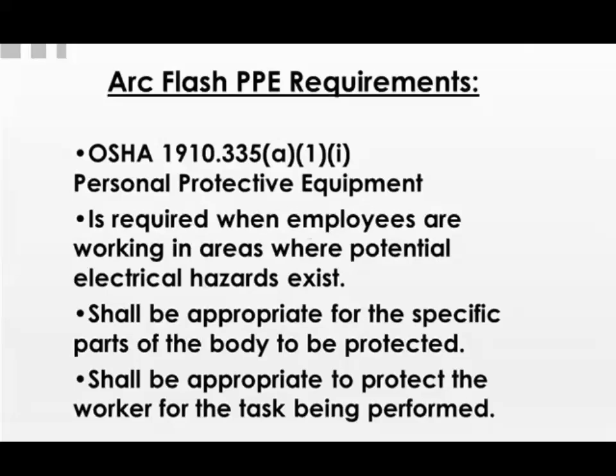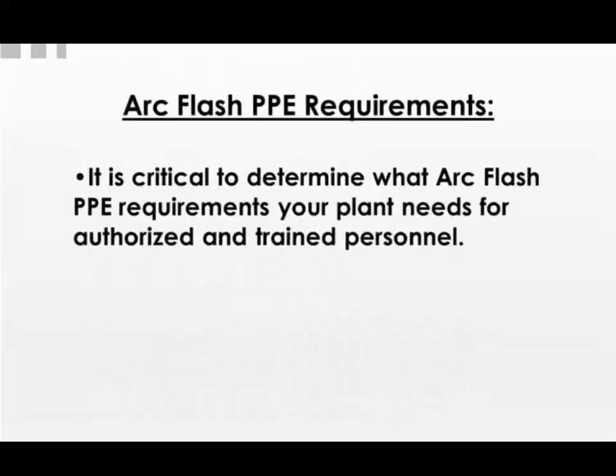So OSHA requires that PPE, when employees are working in areas where potential electrical hazards exist, shall be appropriate for the specific parts of the body to be protected, and shall be appropriate to protect the worker from the task being performed. So it's critical to have that arc flash hazard analysis done to know what the arc flash hazard rankings or ratings are, and that the arc flash PPE requirements meet those arc flash ratings. And again, you train your employees on those.